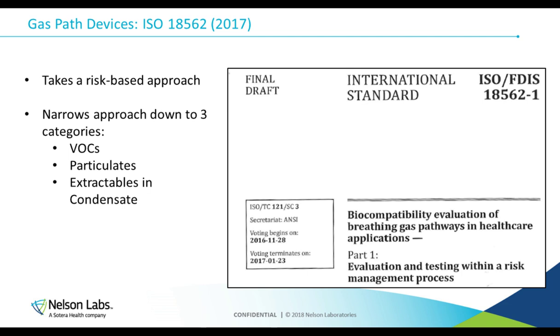So if you're becoming compliant with the MDRs and you have a gas path device, then this slide is really, really important. If you don't already know about ISO 18562, I would refresh yourself on this right away, because to become compliant from a biocomp perspective, if you have a gas path device, then you need to be also compliant with 18562-1. This is a relatively new standard that addresses a gap, or what was a gap before, in biocompatibility for gas path devices. So to evaluate devices that are gas path, you basically can narrow this down to testing in 3 categories for sure: particulates and VOCs. And if the gas path can develop condensation in it, then you should do some extractables and leachables chemistry testing as well.